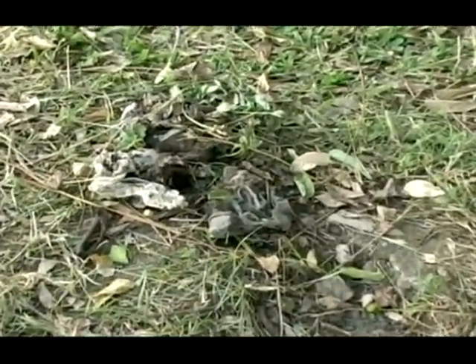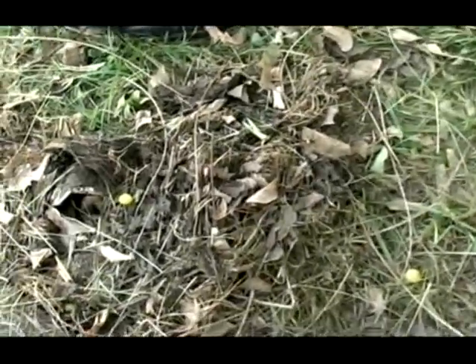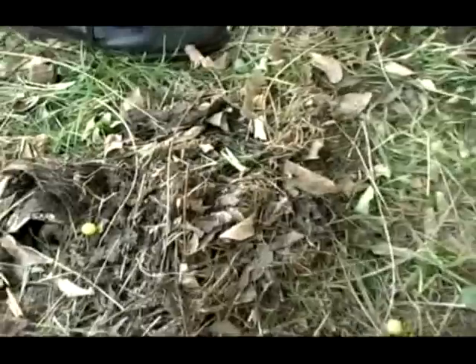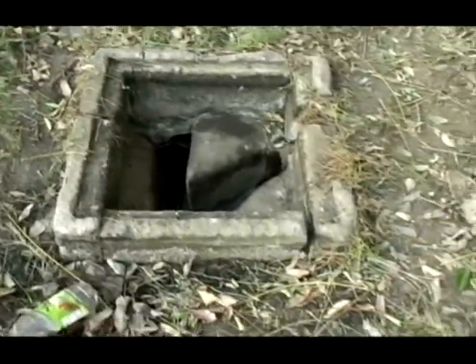If you look at the debris here, some of it includes sanitary napkins and female sanitary pads — all this is the stuff that came out of the hole when they cleared it this morning. Right now, if you flush the toilet, you would notice that the sewage passes right there in plain view. Fifty years ago when this was built that was acceptable, but it is not according to the building code now — you can't have open sewage passing through boxes like that.